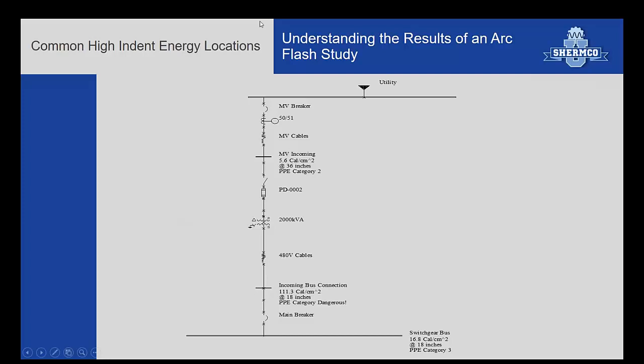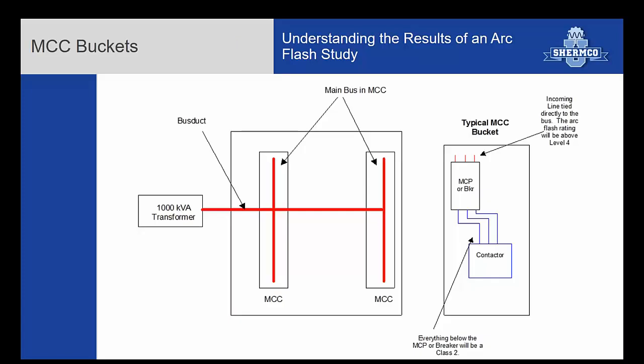So here's an example of a typical medium voltage transformer being fed by 13.8, step down to 480. The zone we're talking about is from the transformer to this main breaker. If you see here, this one was estimated at 111.3 calories. That's well over 40 calories, so it's very hard to have protective gear to work on. And these are very common things that we see throughout the industrial plants. Here's an example with transformer feeding some MCC buckets.